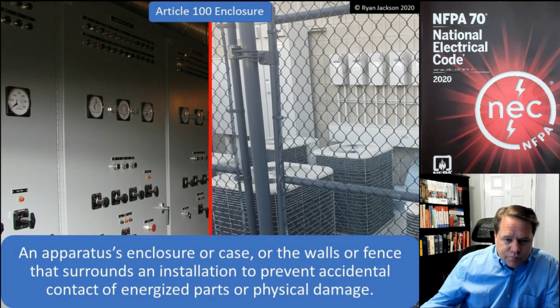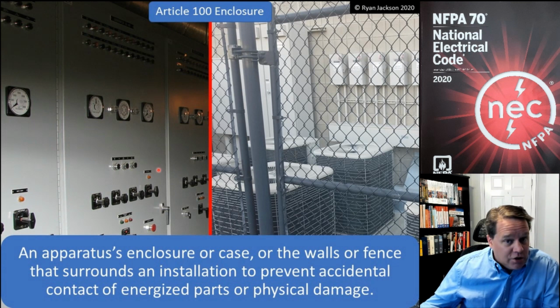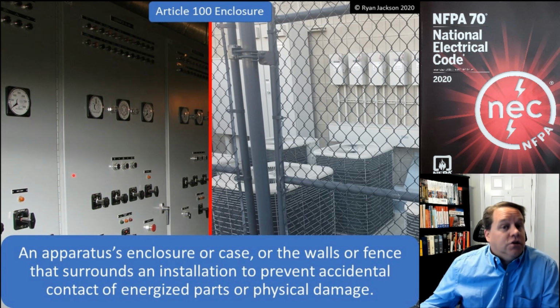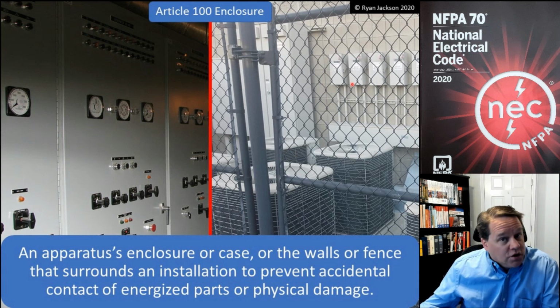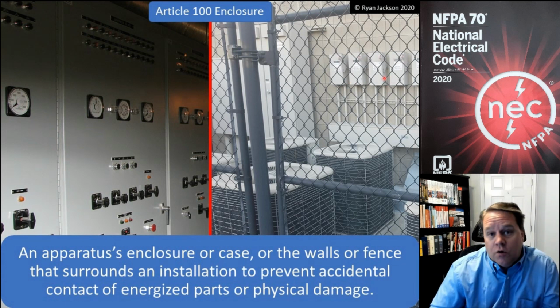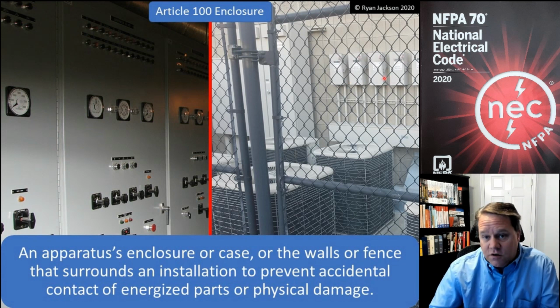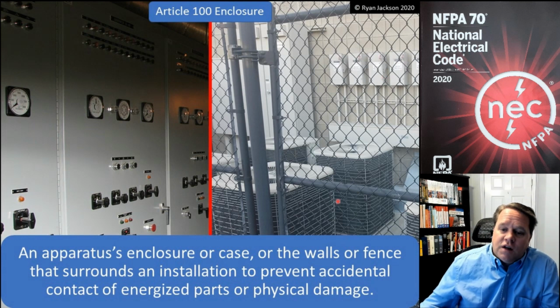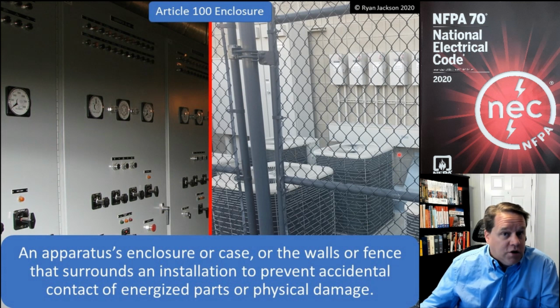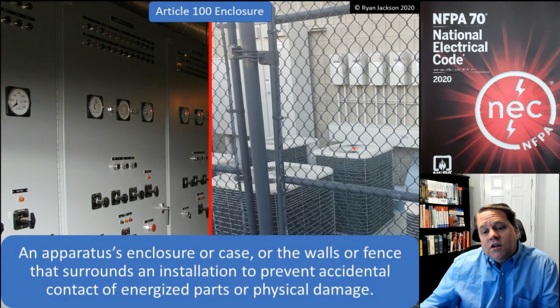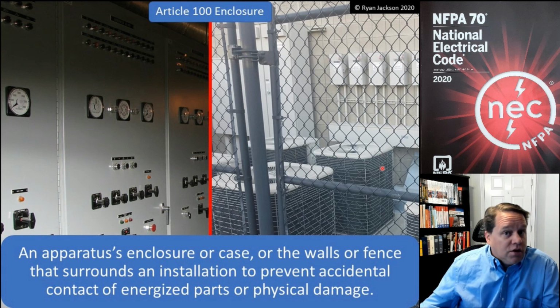All right, so here on the left we have some switchgear. This is definitely enclosed, no question about it. Back behind this chain link fence, you have some disconnects that are enclosed, right? The actual switching devices are enclosed in a cutout box, and that's the enclosure for it. The electric motor inside of the air conditioning unit is enclosed by the unit itself, but interestingly, the unit is enclosed as well by the fence. So a fence can be an enclosure.